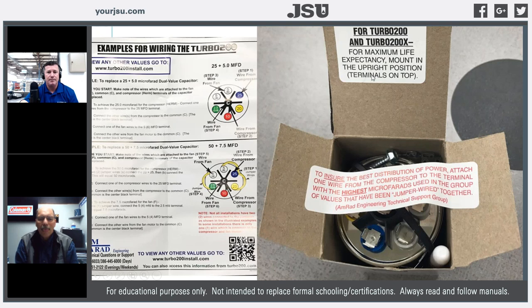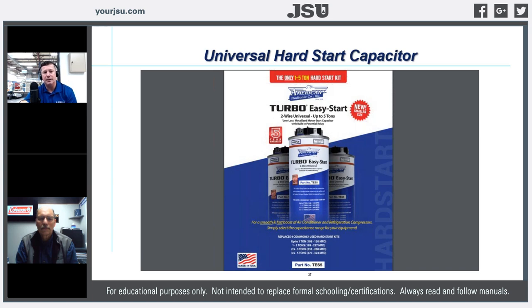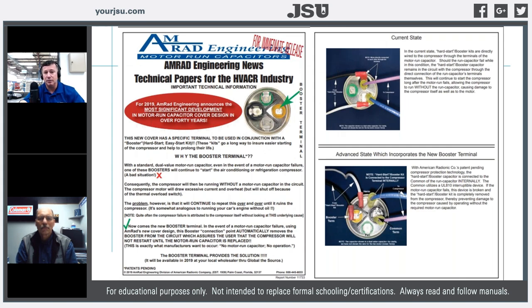There are lots of combinations you can use on that capacitor. One product I'm very excited about that Turbo is releasing is the Turbo Easy Start — a multi-purpose hard start kit usable between one and five tons. The current hard start kits depend on the tonnage of the equipment, but the Turbo Easy Start functions between one and five tons with multi-horsepower ratings depending on jumper tap placement, similar to the Turbo 200 and 200 X.